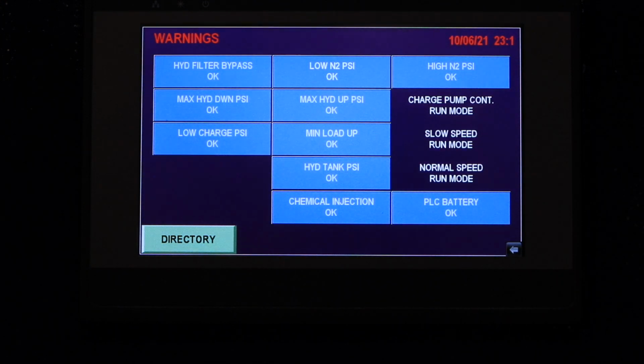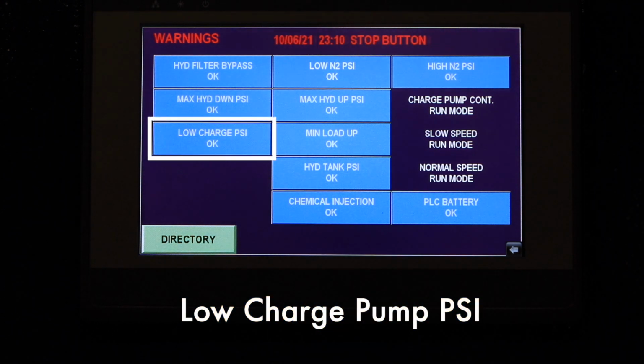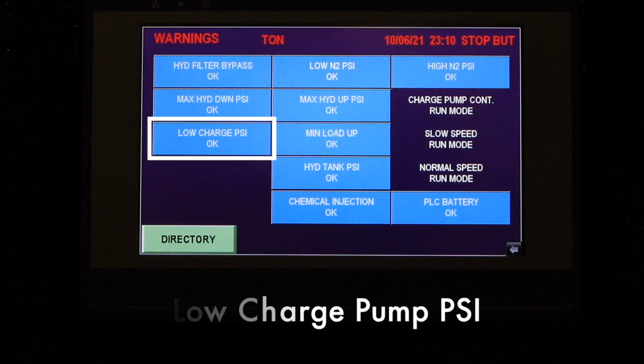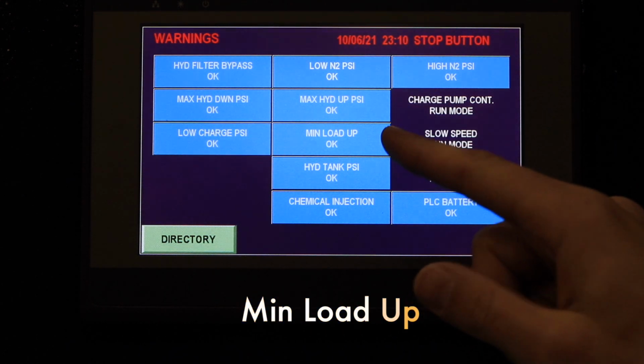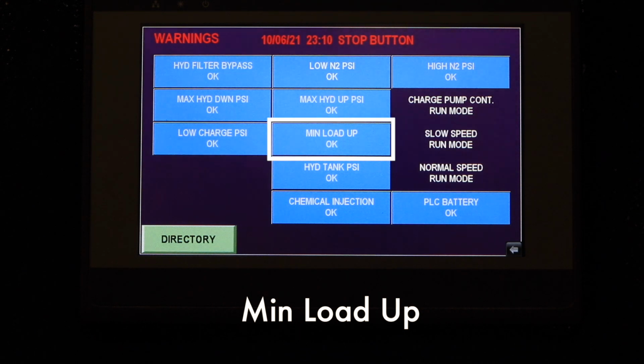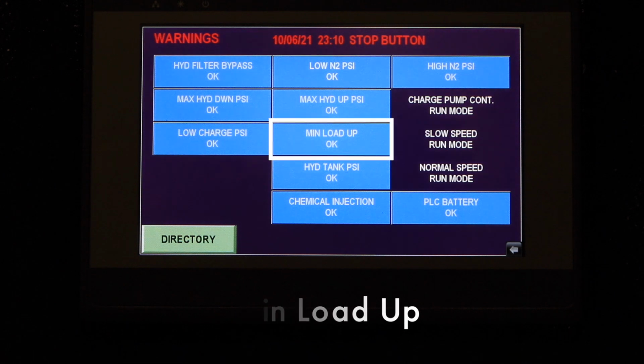Next up is the low charge pump PSI. This warning will activate if the charge pump is not able to get the hydraulic system up to its defined pressure. Next is the min load up, which, as its name indicates, will give a warning if the measured rod load drops below a certain value. Along with this warning, there's also a min load alarm that will shut the unit down if a rod break is detected and the load drops significantly.